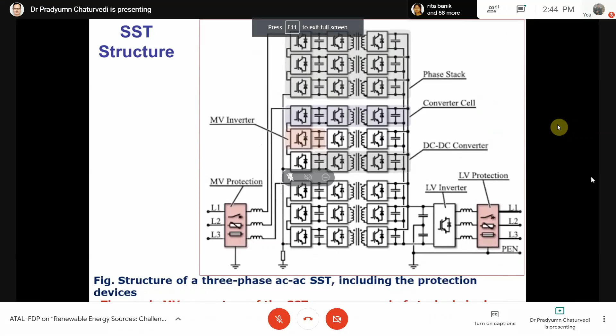So module number 1 has all converters in a single module: rectifier, inverter, which inverts at high frequency voltage and gives it to the HFT. Then rectification happens again, so AC, DC, DC, AC, AC, DC. So you have this common DC bus here, and in every phase you have to connect and integrate all such modules.